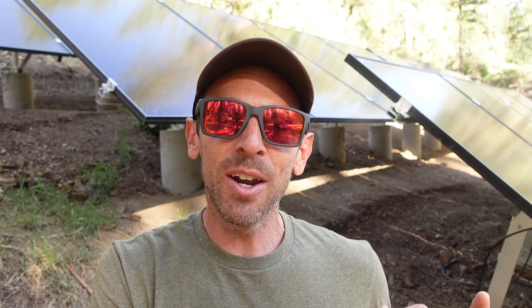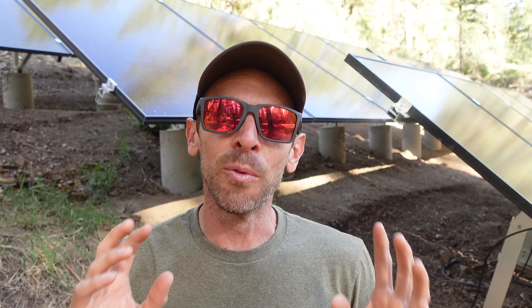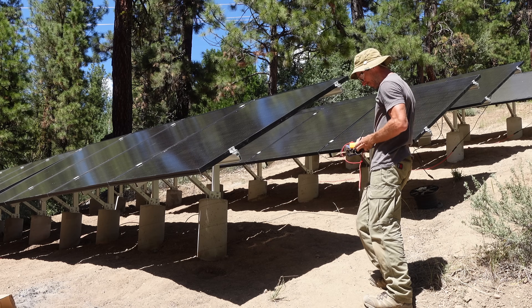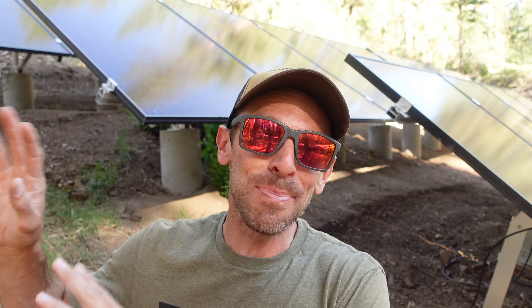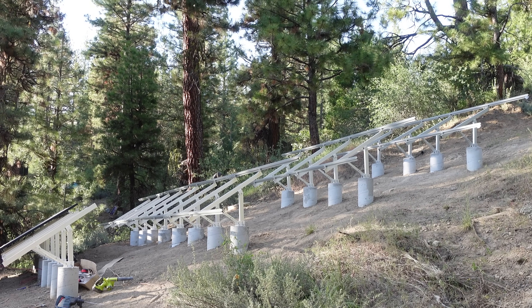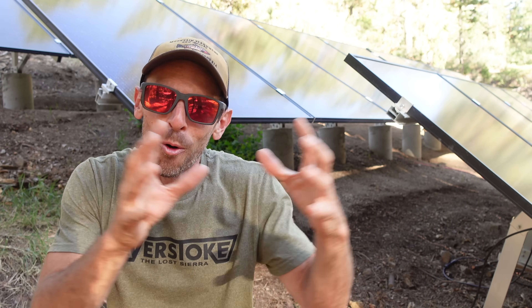The math of balancing the inverter and all the voltage works pretty good with two separate strings of 12 panels. These are 400-watt panels from Canadian Solar — I bought a whole pallet from Signature Solar, a great place to buy your DIY solar products. With 24 panels at 400 watts, the potential upper end of this system is going to put out 9.6 kilowatts. I don't know if I'll ever see that amount — I'm not perfectly aligned south and I'm keeping the panels at a 30-degree slope year-round. On top of the concrete piers I used the EG4 bright mount solar racking system — pretty easy, just time consuming when you have to do six of them, four panels per rack mount.